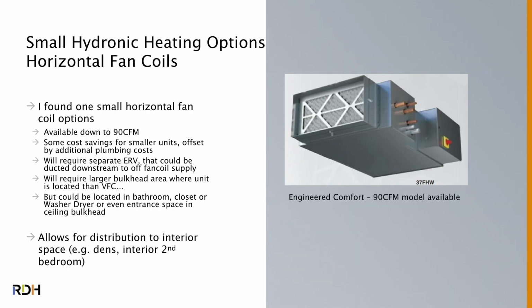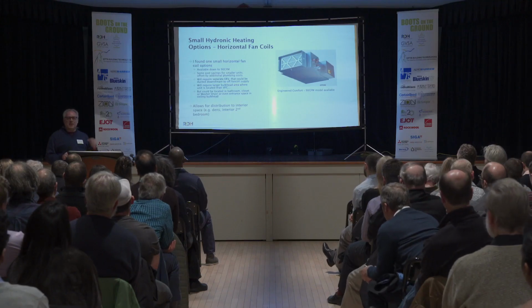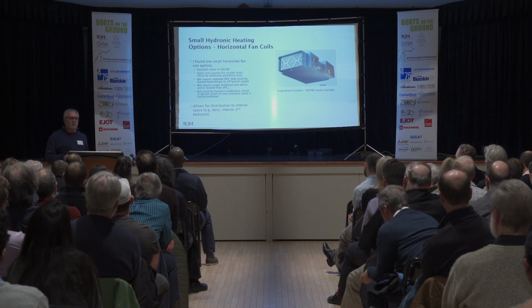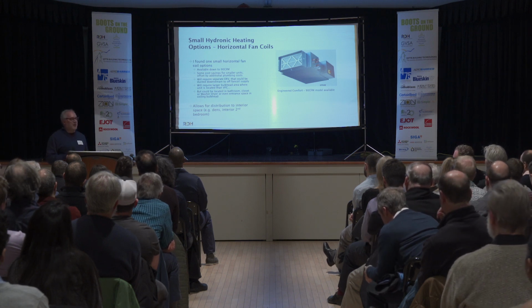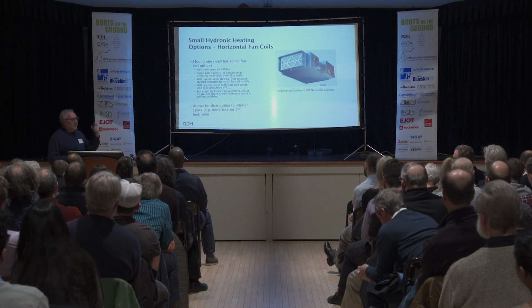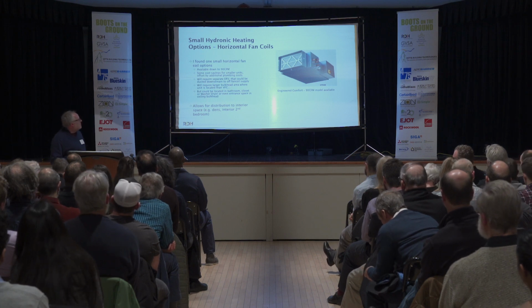In-suite options. Most of the market is into those vertical fan coils. We can't find them small enough. I did find a horizontal fan coil, only one, after several hours of Google searching, down to 90 CFM. This is actually sized to heat and cool a passive house suite around 750, 800 square feet. You'll need a little larger bulkhead where you install this, which means you might be considering moving it to, say, the roof of the bathroom, or the roof of the washer-dryer closet, or someplace that already has a drop ceiling. So you don't have as large a bulkhead in the living space, but you can do that.